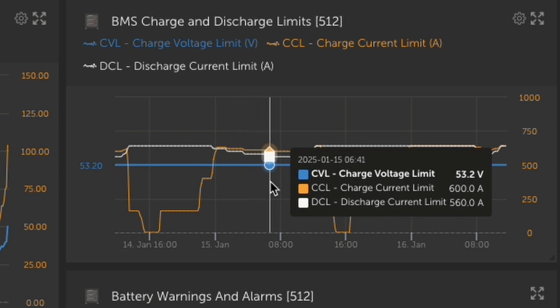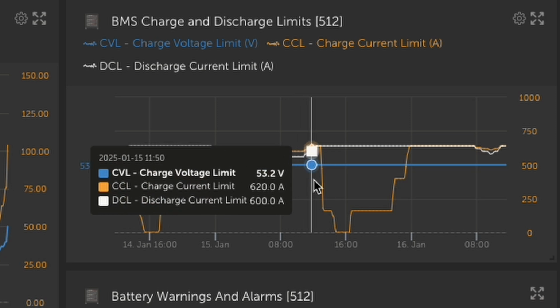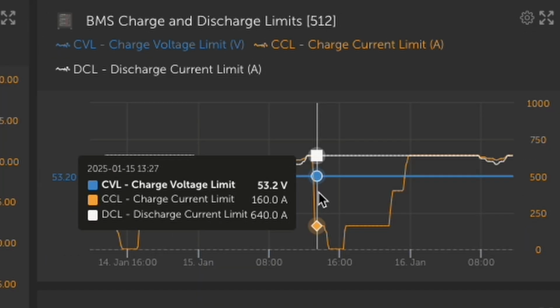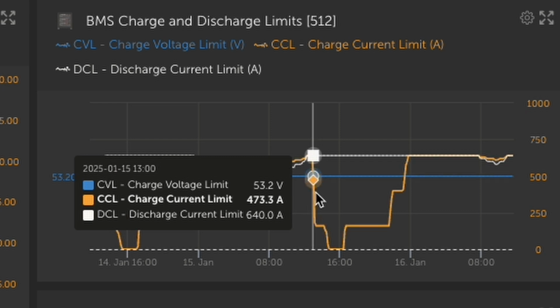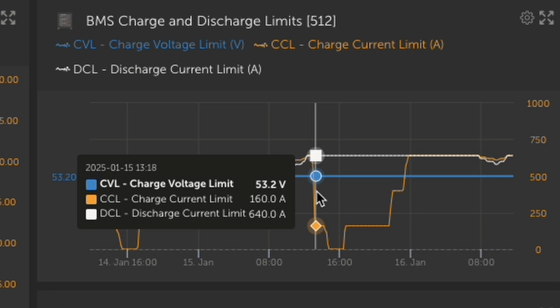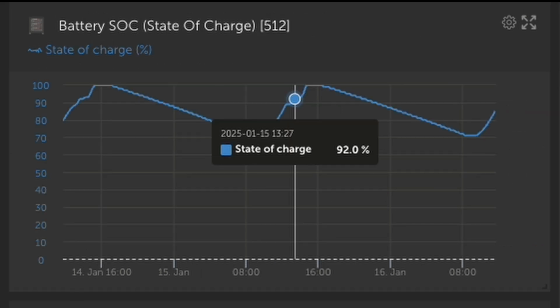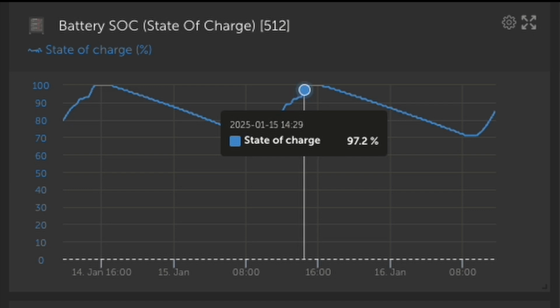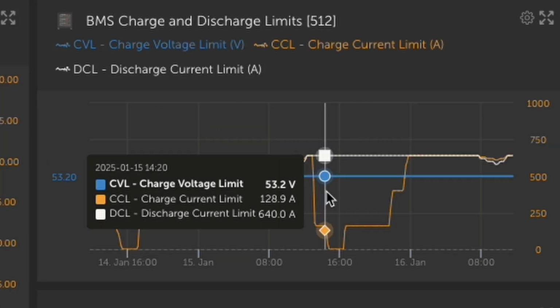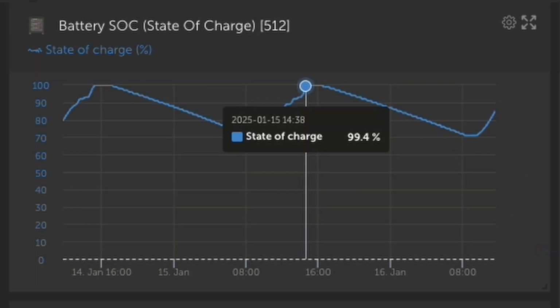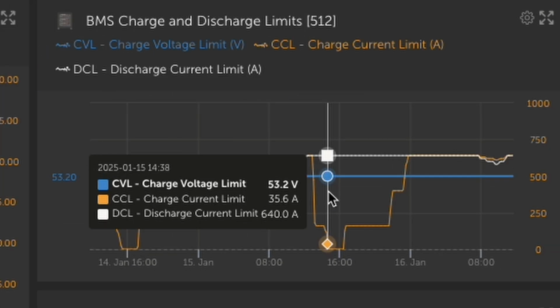Now, as we went through the day, you'll see here as the battery approaches 90%, this charge current limit begins to drop. This is the battery going from kind of a bulk cycle into more of a top-off absorption cycle. That charge current limit is still a pretty significant charge current limit. That's 160 amps total, which is almost everything that our solar can give it, but is spread across 8 batteries. Now, as the battery bank reaches full, as soon as it reaches 99%, that current limit drops a little bit more, and at 100%, the charge current limit drops to 0 amps.